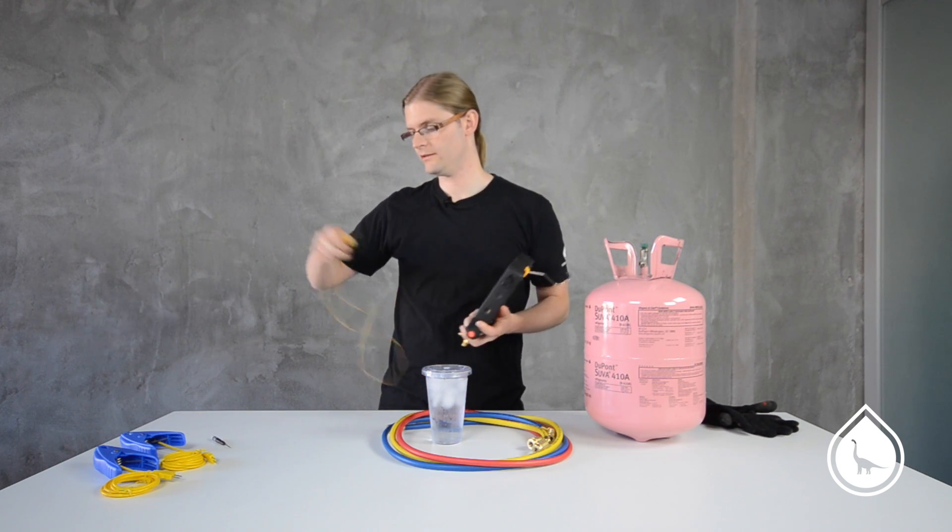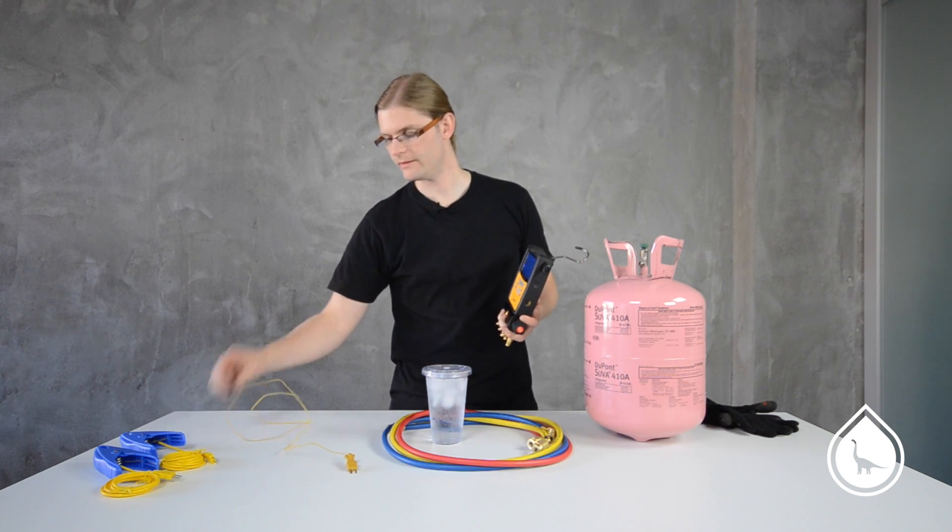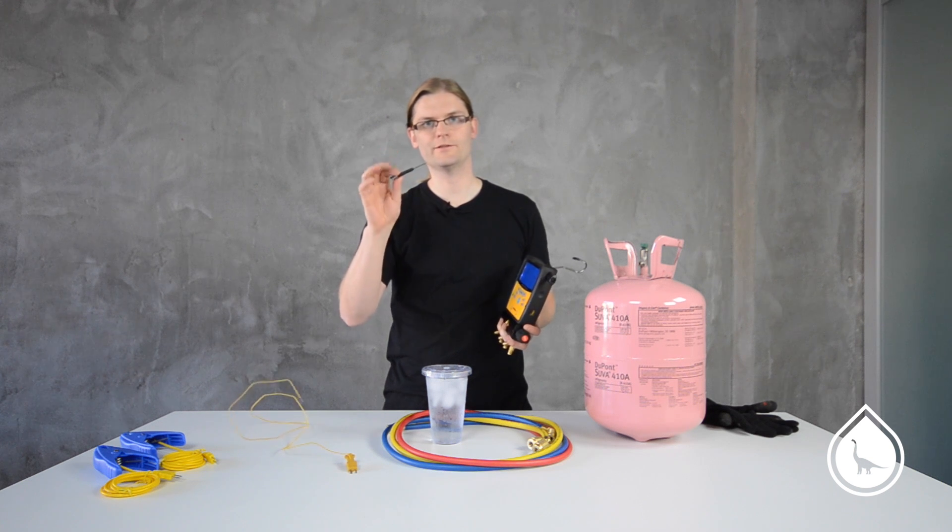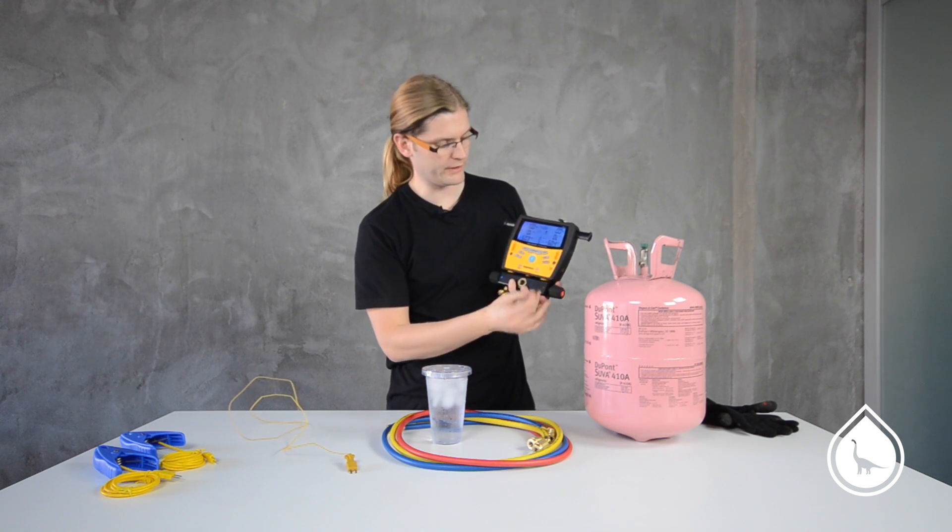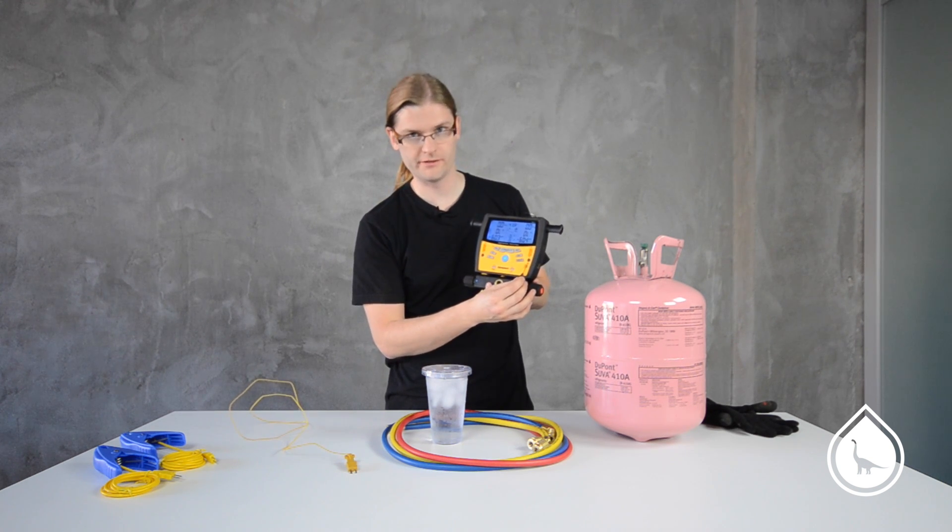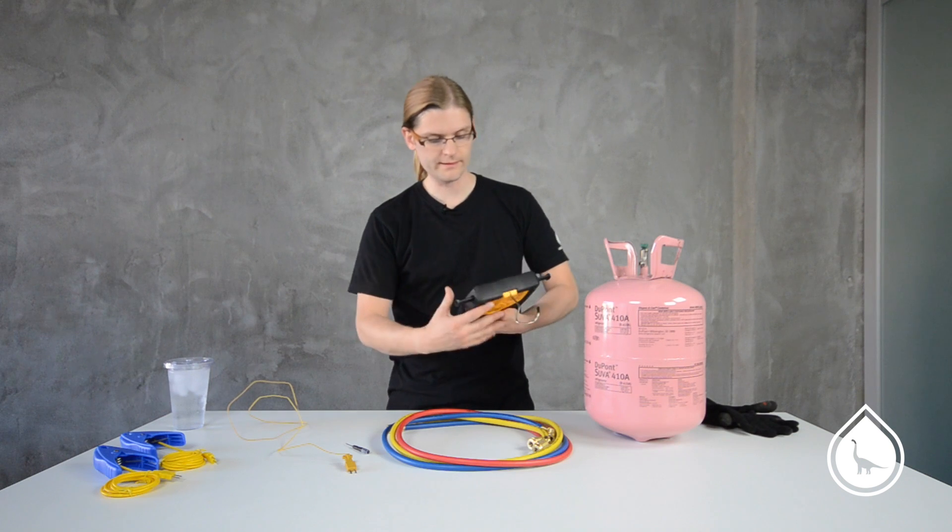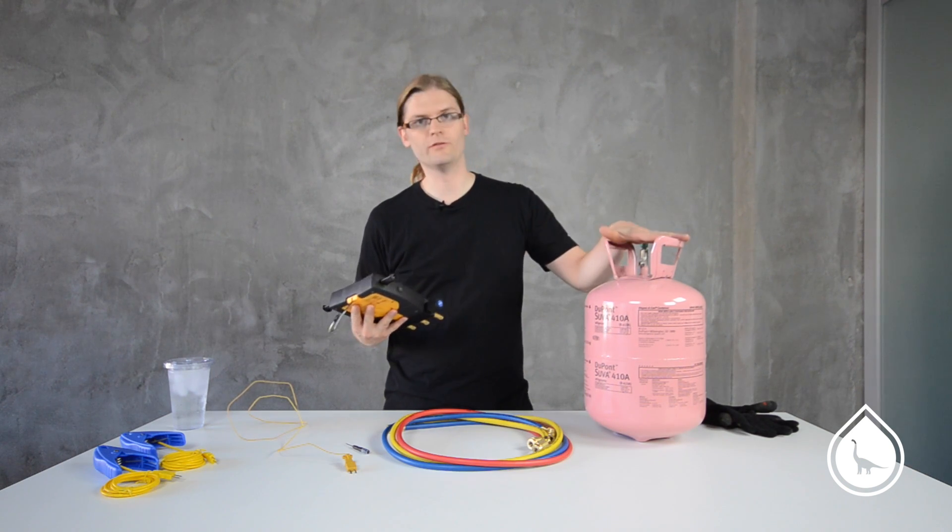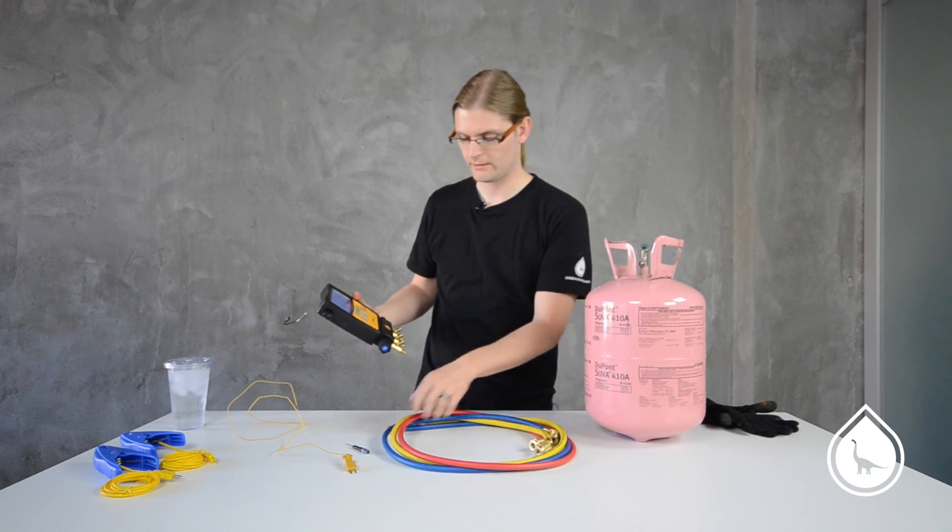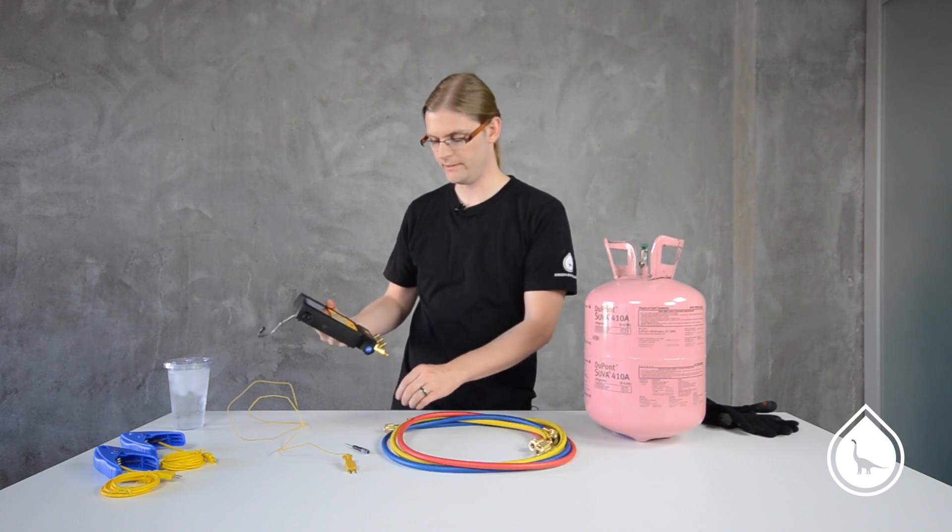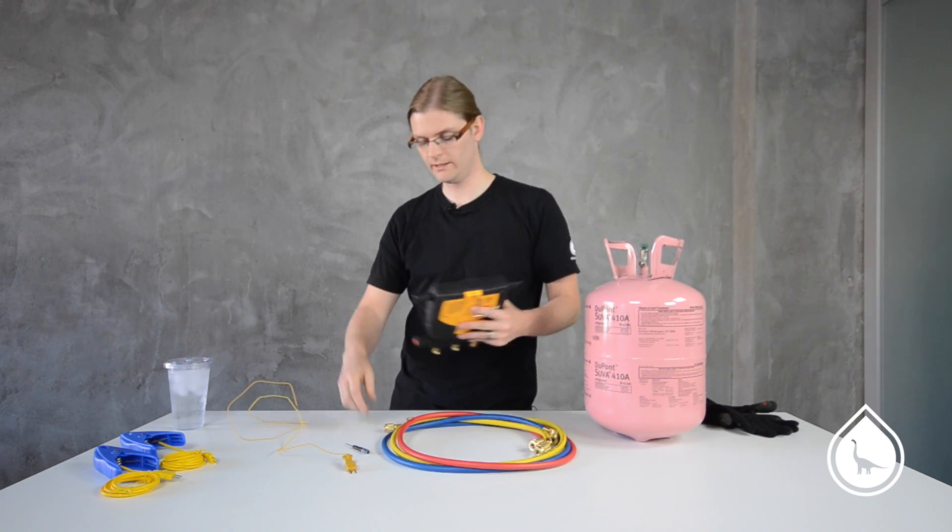If those are reading off and they need to be adjusted, you'd grab your flathead screwdriver, put it in the calibration potentiometer here, and give it a little twist either clockwise or counterclockwise until your temperature reads right around 32. So the next step is going to be to connect to our refrigerant and compare our readings to an actual PT chart.